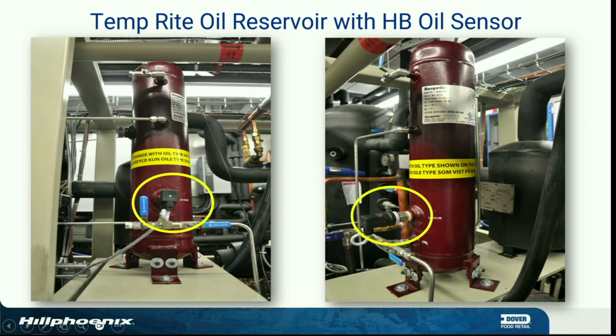You go from a flashing green to a solid red. All right? That means you have fluid present, and now we're going to either transfer it, or it's telling us in the reservoir that we're full, we need to stay full. The ones on the oil separator and the ones on the flash tank are not interchangeable. They're different. The rod's even bigger because it needs more surface area.